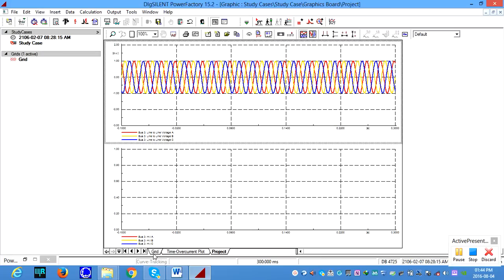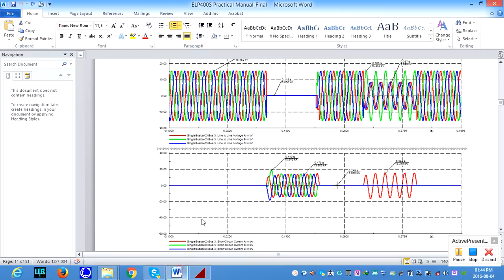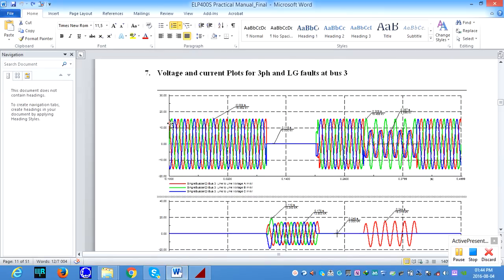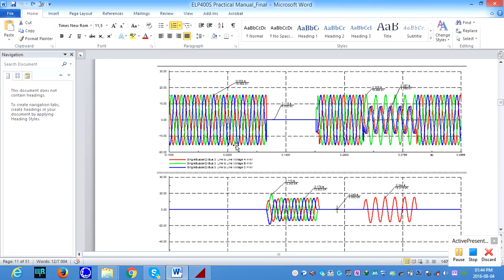Next we need to apply a fault. To define the fault, according to the memo, if you look here, we are creating different scenarios to validate the three phase and line to ground events. In this case, from 0.0 to 0.1 seconds, there is no fault in the system. From 0.1, there is a three phase short circuit. It means that voltage goes down and the three phase currents build up here. But without fault condition, the current is 0 up to 0.1 seconds. Okay. From 0.1 second, the fault is building up, and the fault is in the system for 0.1 seconds. So at 0.2 second, the fault is cleared.